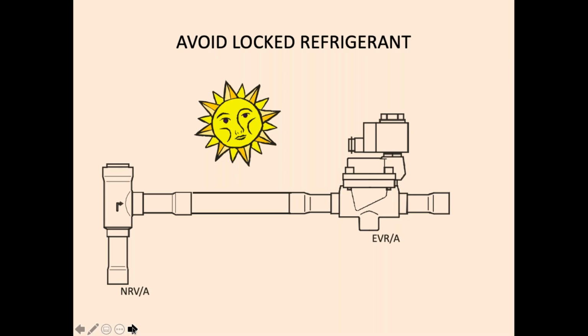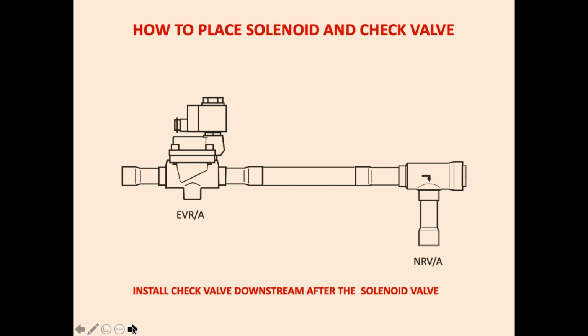If the solenoid valve closes, the liquid will get trapped because it cannot return back. And if the ambient temperature goes up, your pipeline will burst. This liquid is trapped, and when temperature increases, its pressure will increase, and the pipeline will burst. So very important, either provide a safety valve on the liquid lines or do the piping in this manner: solenoid valve and then your NRV, so that NRV is always open. Even if your solenoid valve is closed, liquid ammonia will not get trapped. This is one of the major reasons of accidents.